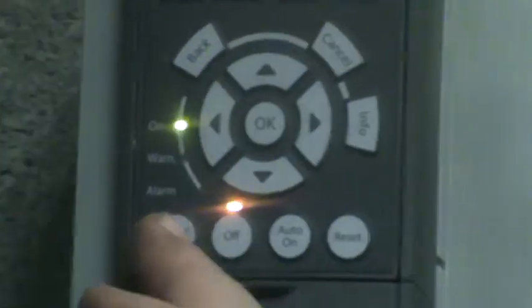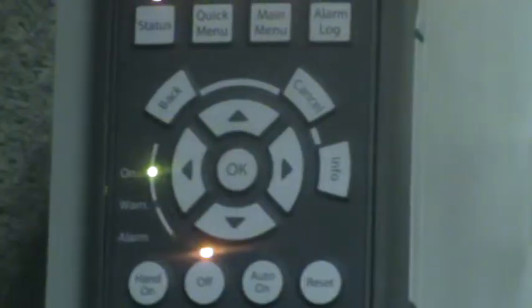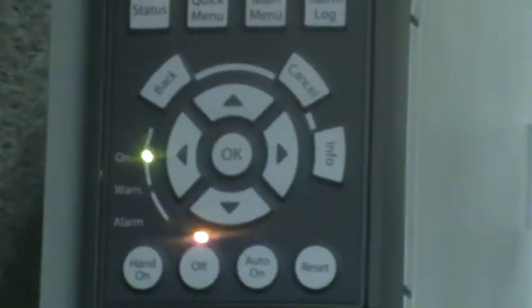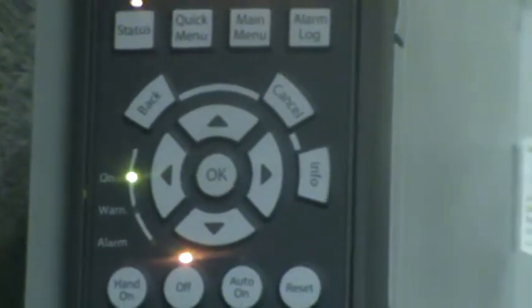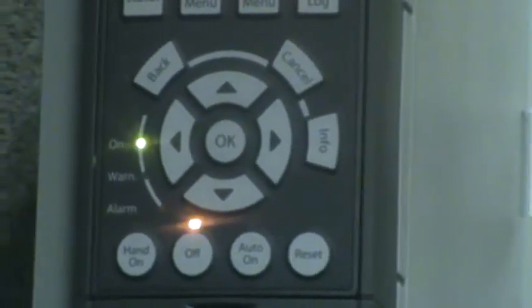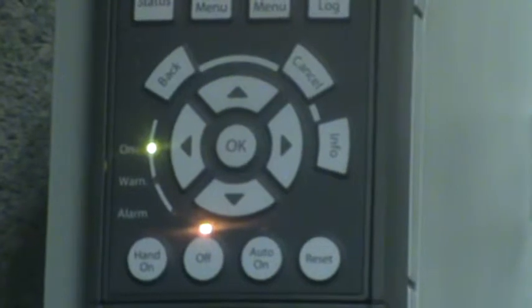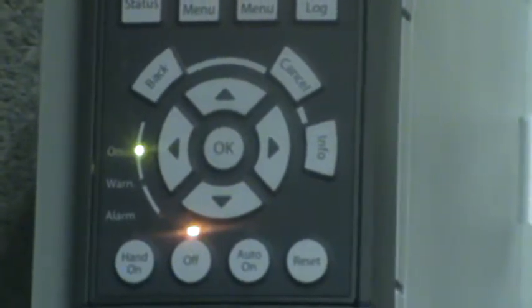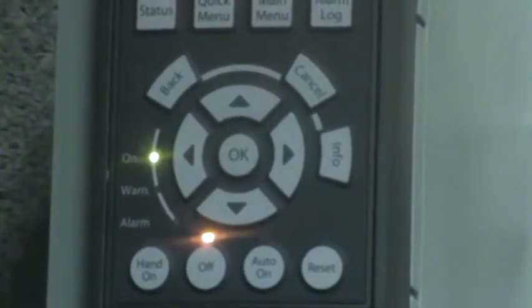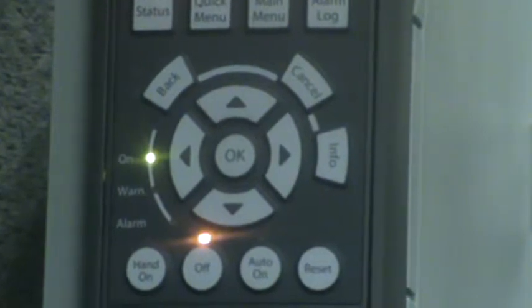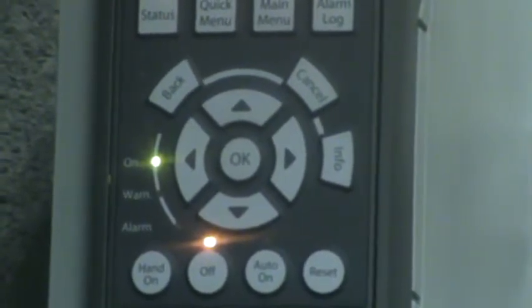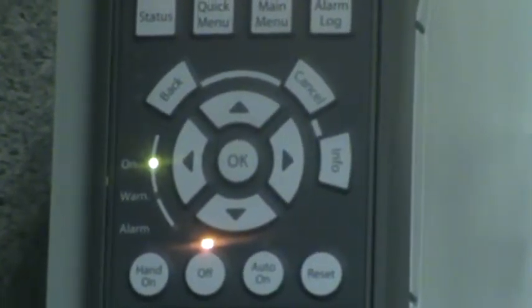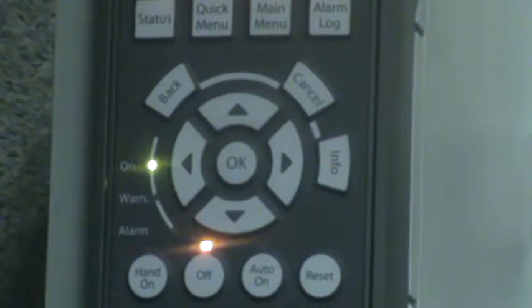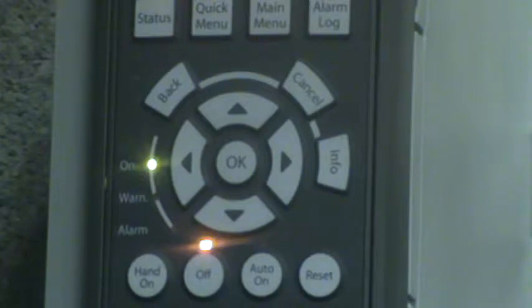You can run it in hand, which will take the transducer out of the circuit, and you'll have to select the speed by hand, just using the arrows up and down to tell you how fast you want to go. You guys have to do maintenance, or if you have a transducer failure or problem. Now you come in one day, the whole building's cold, and they're just sitting here doing nothing, but they're on. Hit the hand, crank it up to whatever speed you think will work for that day. That'll get the heat moving, and then you guys can start doing your troubleshooting and stuff.